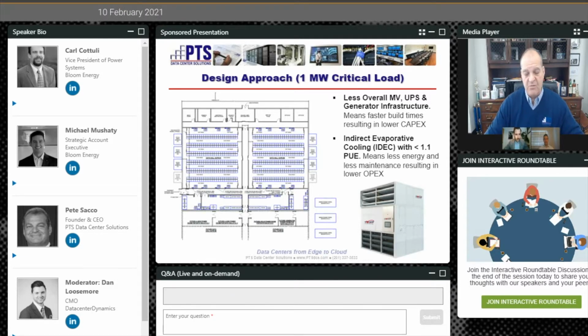You'll notice how much of the cooling infrastructure is inside the room? Zero. It's all sitting outside the room. So the one on the left is a 500 kW operating load. You could sell that because it's operating with N plus one redundancy, three 250 kilowatt boxes. And by the way, it's scalable to turn it into a 750 N plus one. So that's a 500 kilowatt data hall number one.